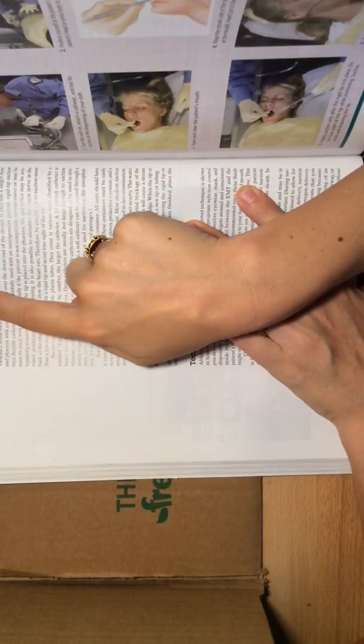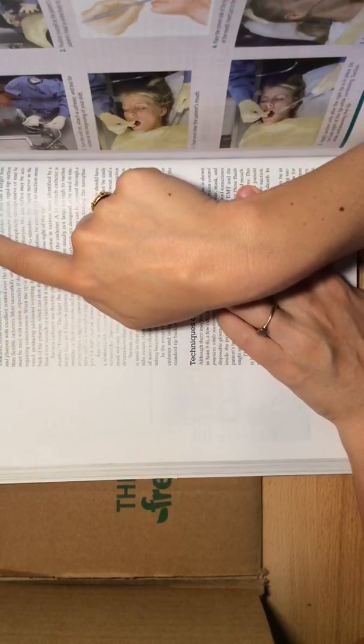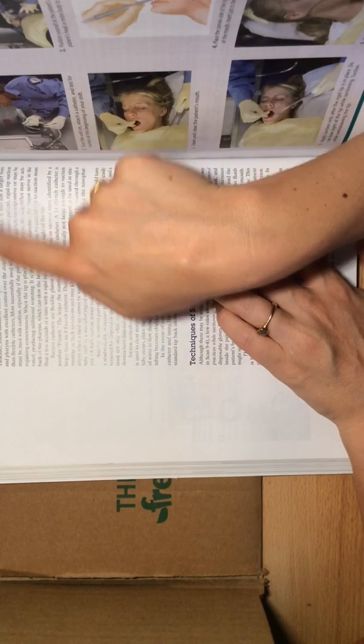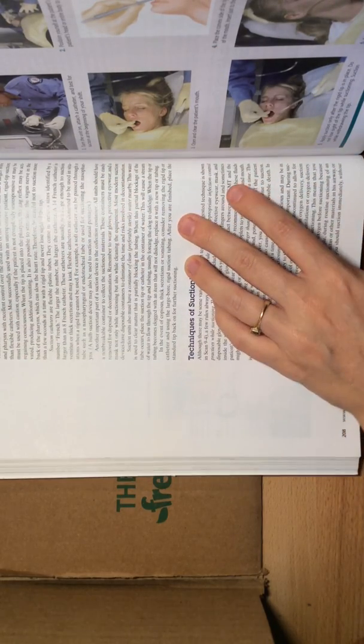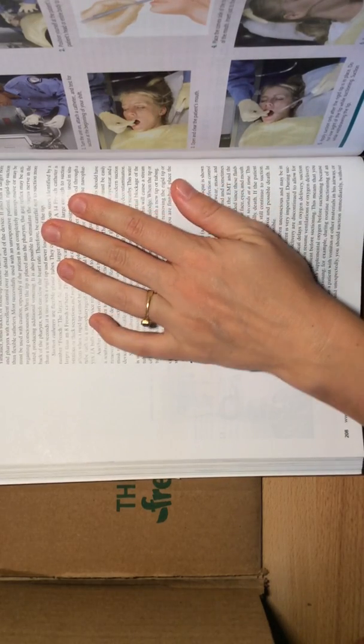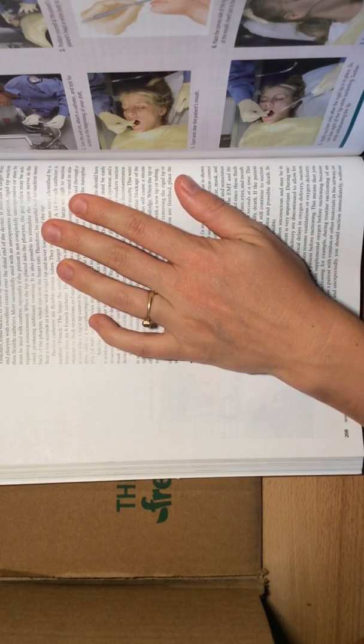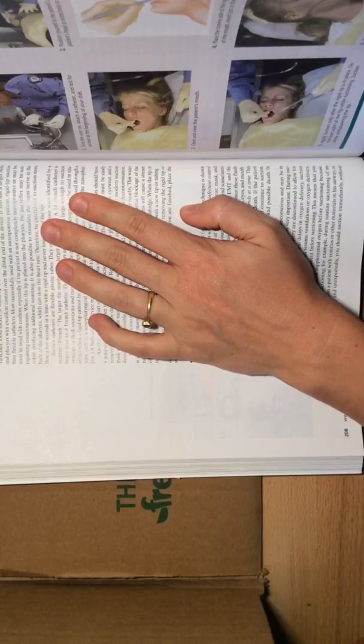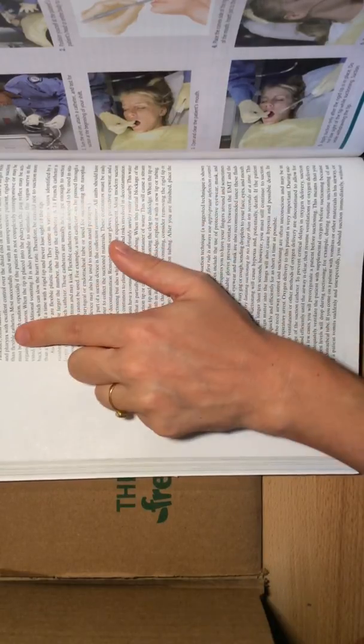The tubing attached to a suction unit must be thick-walled, non-kinking, wide-bored tubing. This is because the tubing must not collapse due to the suction, must allow chunks of suctioned material to pass, and must not kink, which would reduce the suction. The tubing must be long enough to reach comfortably from suction unit to patient.